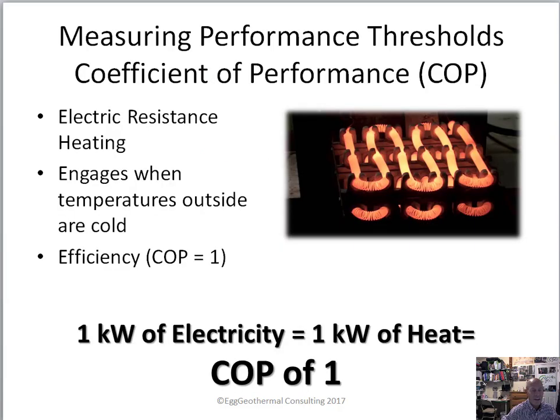In order to understand heat pumps, I think it's important to understand how heat pumps are rated. First of all, in energy consumption, appliances and equipment are normally rated in coefficient of performance. The coefficient of performance is important in that it shows how much energy is consumed and how much energy is produced from an appliance. In the case of electric resistance heat strips, one kilowatt of electricity equals one kilowatt of heat. So electric resistance heat strips such as a blow dryer, a toaster, or one of those little space heaters would have a coefficient of performance of one.